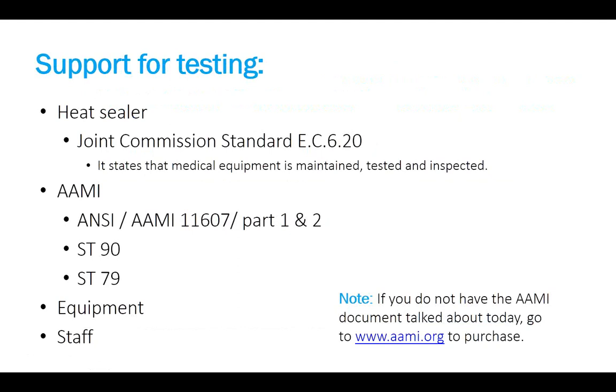Also, the majority of departments use various AAMI documentation, AAMI standards and guidelines. There's one called ANSI AAMI 11607, Part 1 and 2, that deals with sterile barriers, and within it there's a section on pouching. This dovetails into the ISO standard 11607, used in Europe for sterile packaging and specifically pouches. I also mention ST79 and ST90 — 79 probably should have been first — and within those documents they talk about sterilization and pouching, and so on.